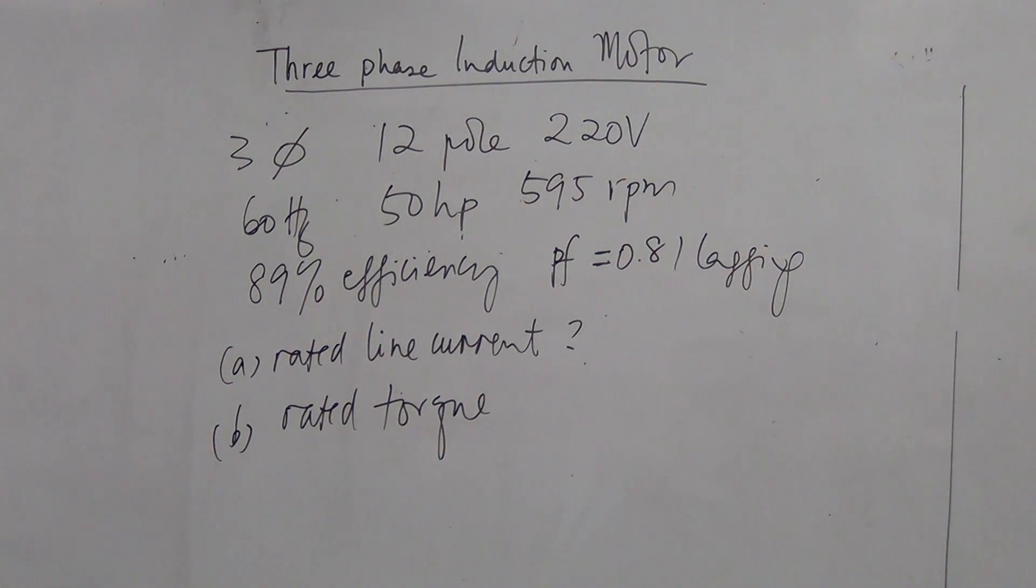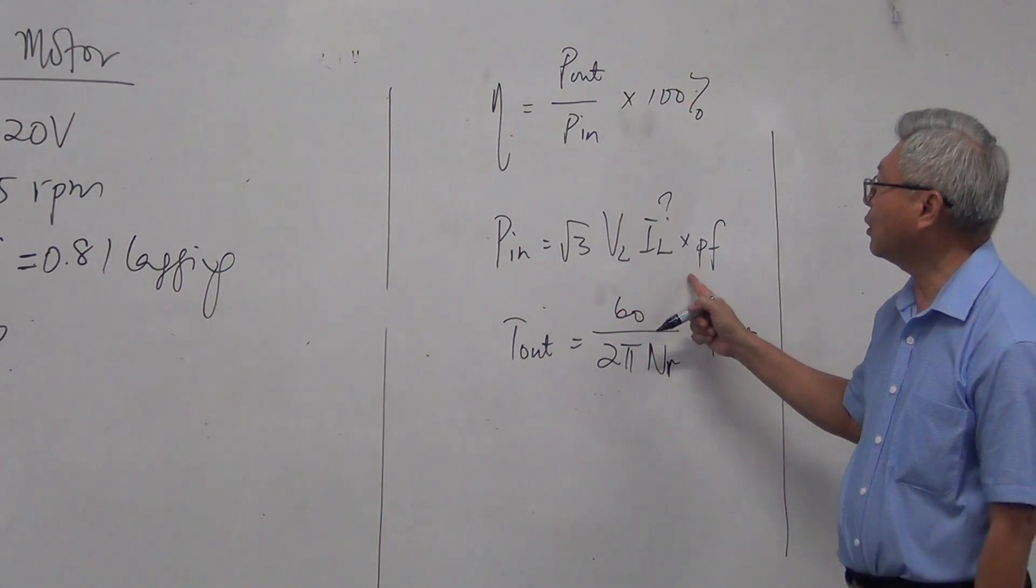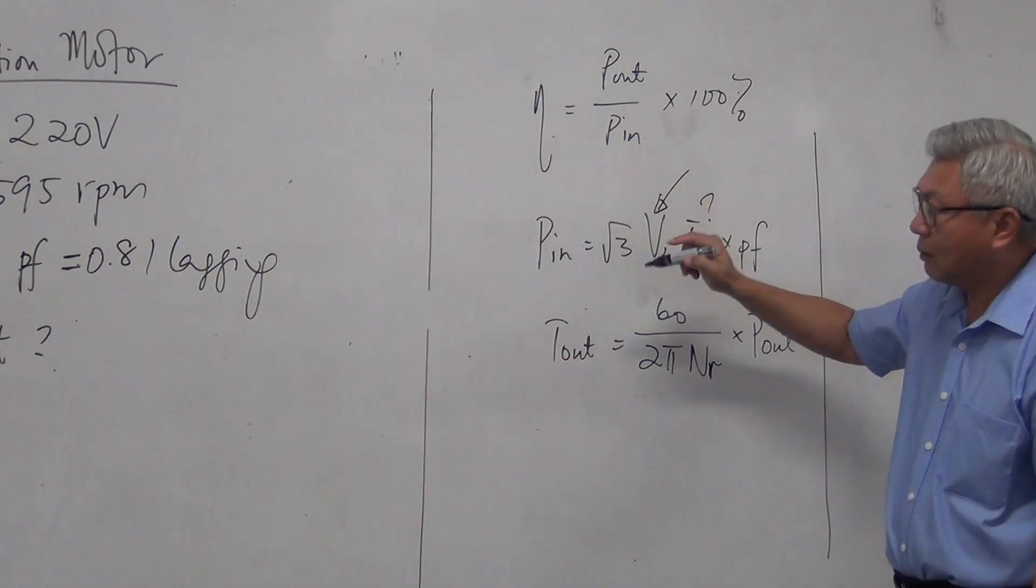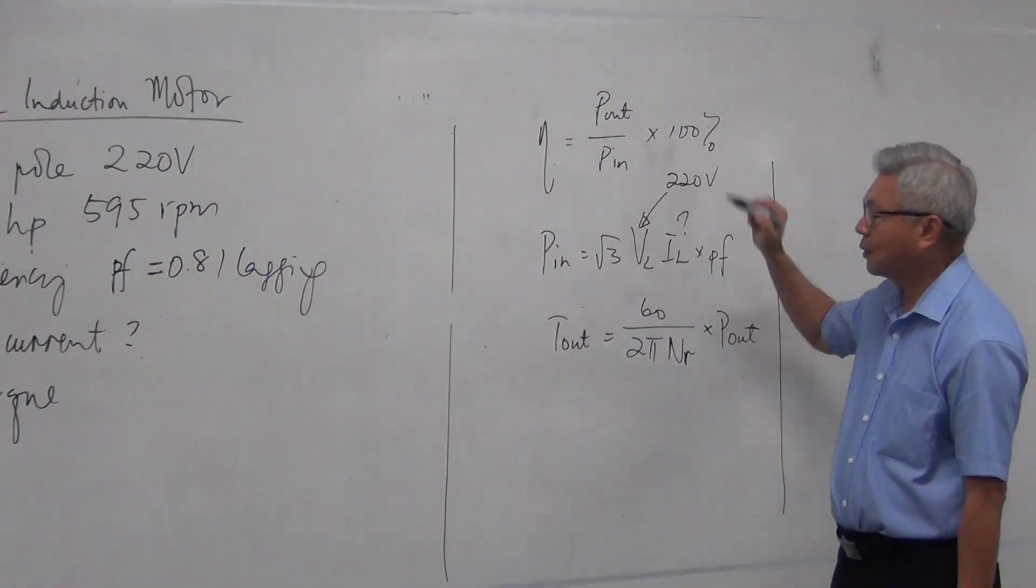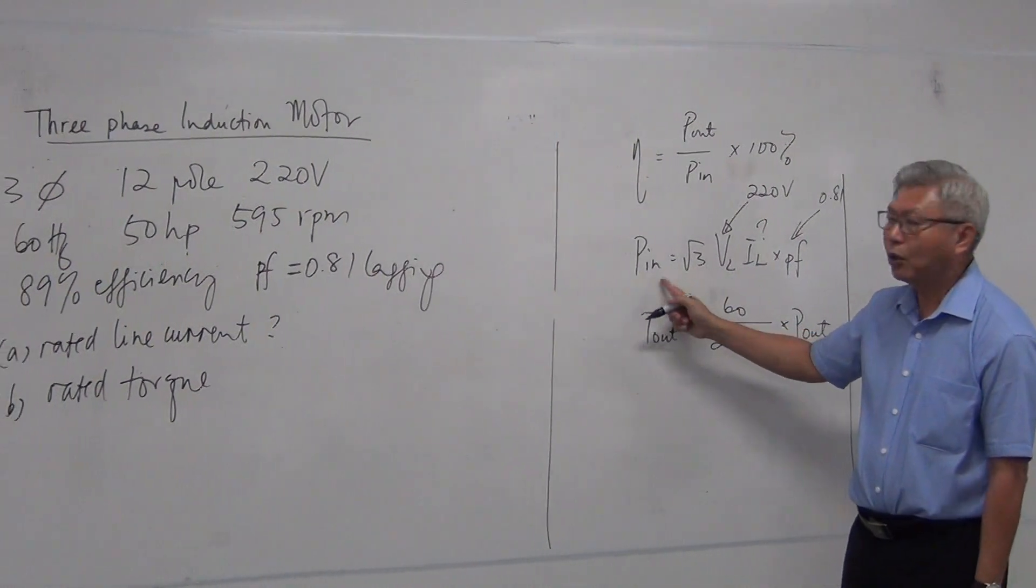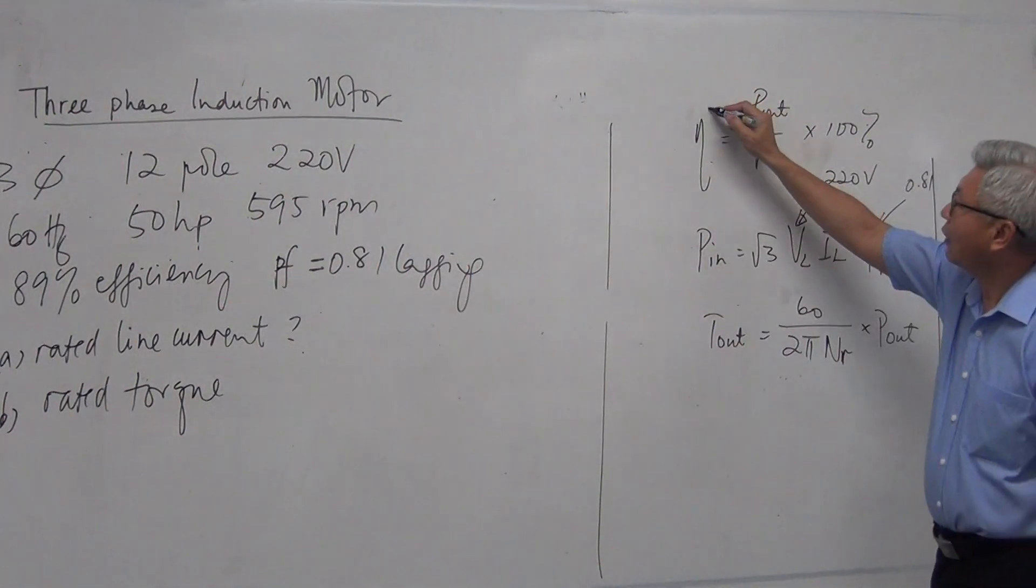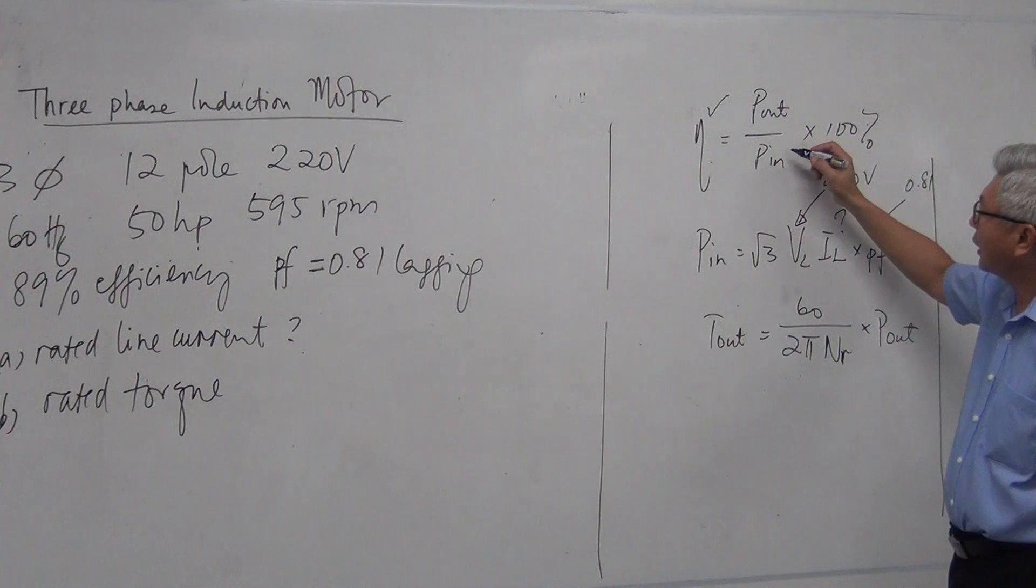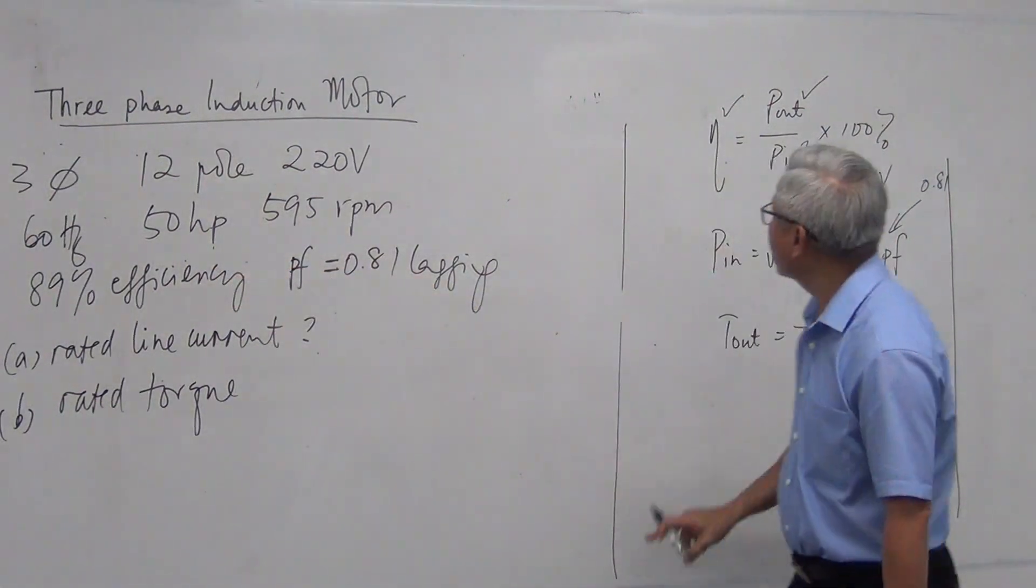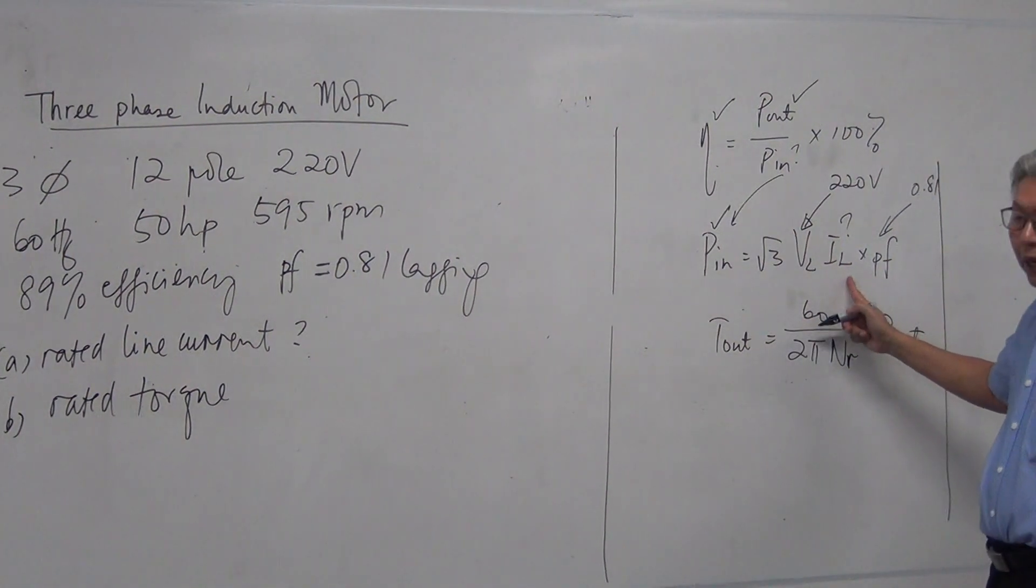Now, look back on our formula here. We need to find line current. In other words, we need to know this. So we need to use this formula. In order to use this formula, we need to know the other parameters. So let's interpret the question. Line voltage, yes, I'm given 220 volts. Power factor is equal to 0.81. Input power, I do not know. But I'm given efficiency. So if I have efficiency and I need to know input power, if I know output power, output power is given, 50 horsepower. So with that, I can find input power. And when I find input power, I put it to here, then my line current can be found.